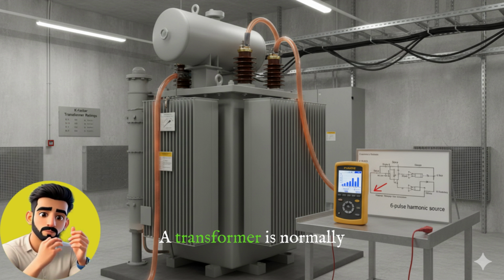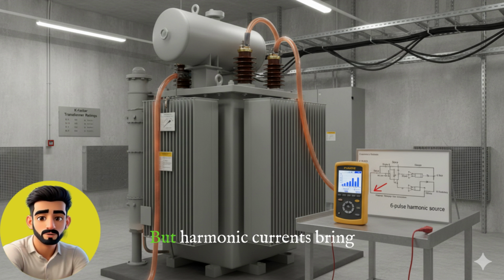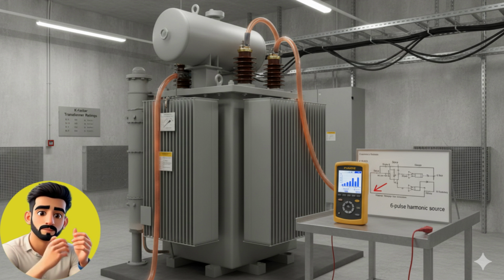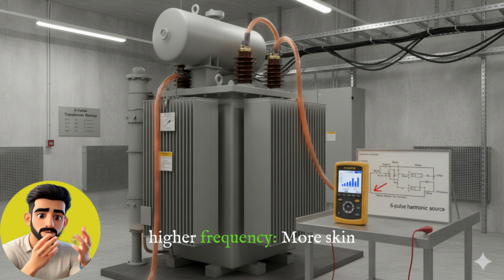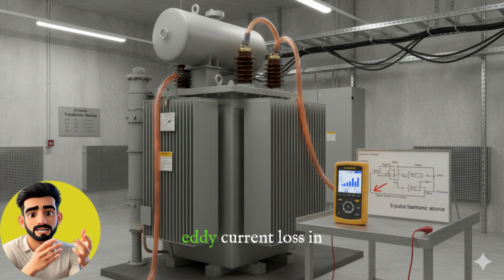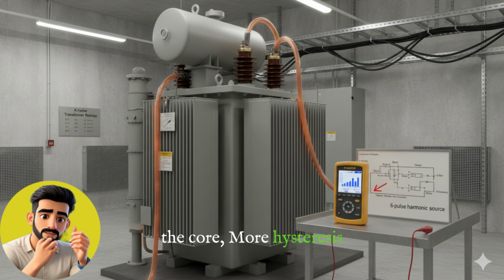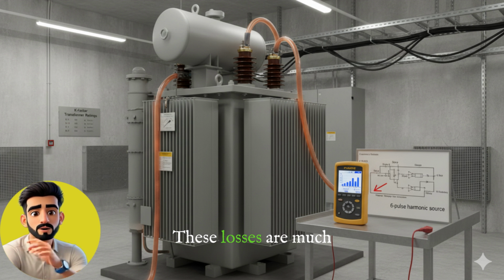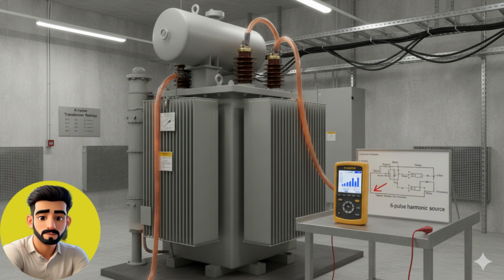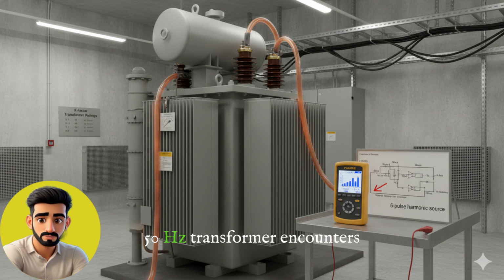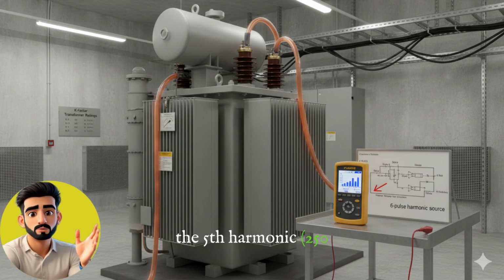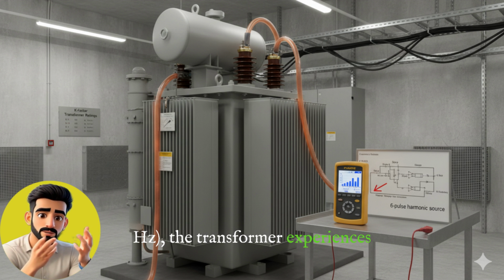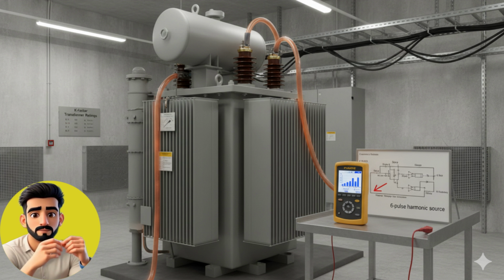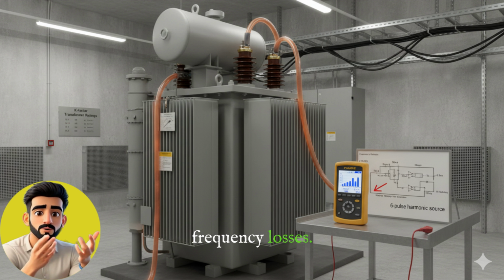A transformer is normally designed for 50 Hz, but harmonic currents bring higher frequency components like 150 Hz, 250 Hz, 350 Hz, etc. The simple meaning of higher frequency: more skin effect in copper, more eddy current loss in the core, more hysteresis loss in the core. These losses are much higher than at normal 50 Hz. Understand this. When a 50 Hz transformer encounters the 5th harmonic, 250 Hz, the transformer experiences stress at 5 times the frequency. Transformers are not designed to handle such high frequency losses.